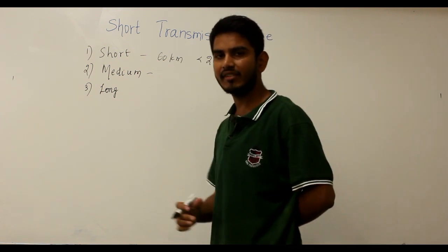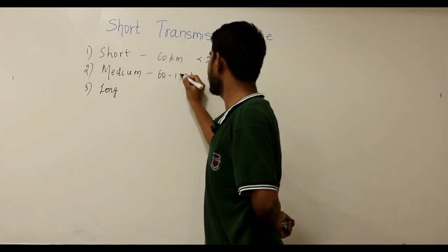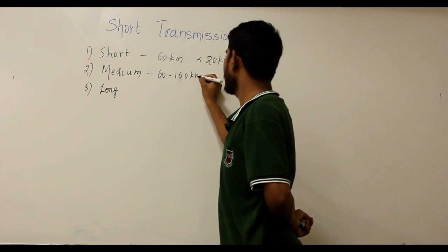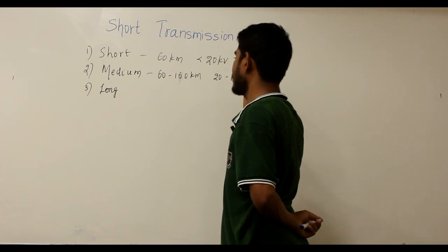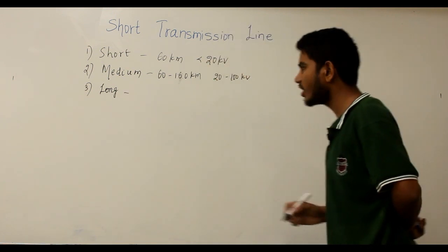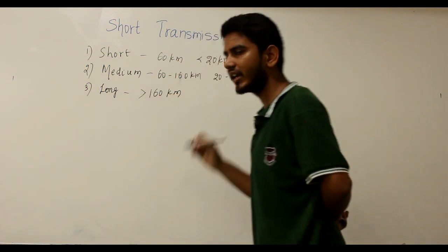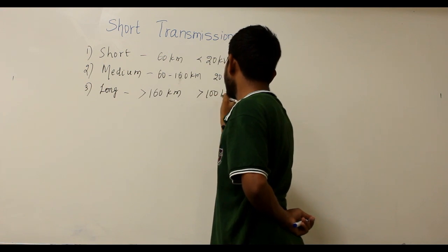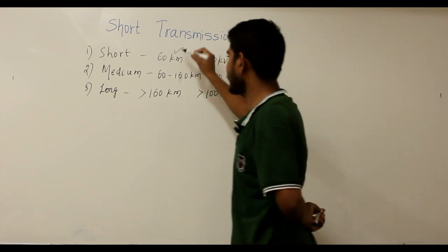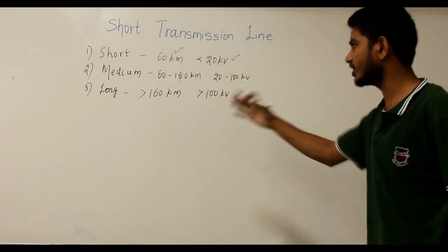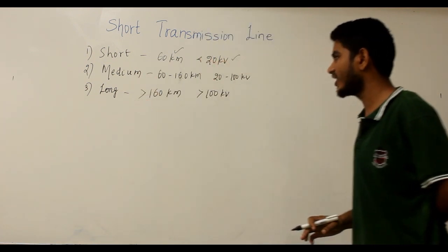Medium distance transmission lines have a line length between 60 and 160 kilometers and a line voltage between 20 kV and 100 kV. Long distance transmission lines have a line length greater than 160 kilometers and a line voltage greater than 100 kV. So based on line voltage and line length, you can classify transmission lines into short, medium, and long distance types.